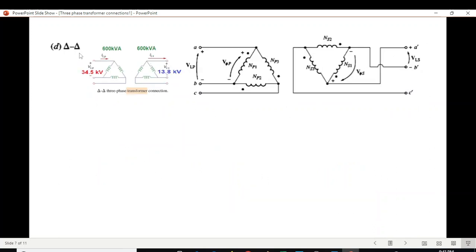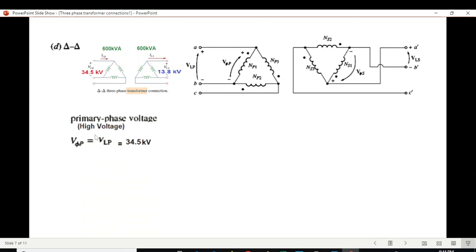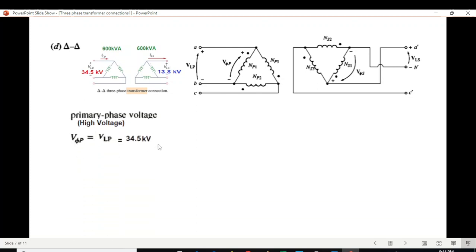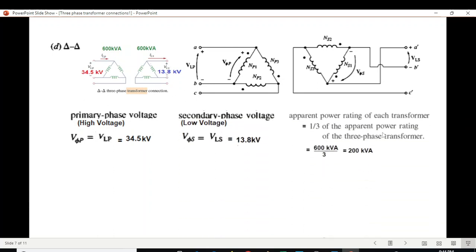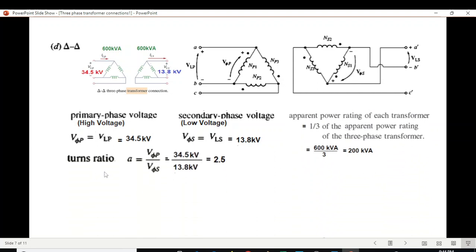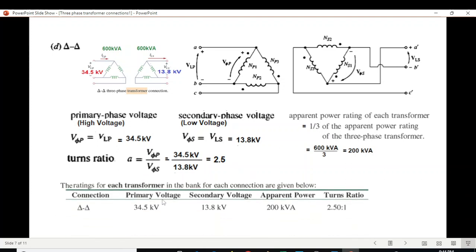The last of the four basic connections is delta-delta. In delta, line voltage and phase voltage are the same, so the primary phase voltage is 34.5 kV and secondary phase voltage is 13.8 kV. Power per phase is 200 kVA, and the turn ratio is 2.5.